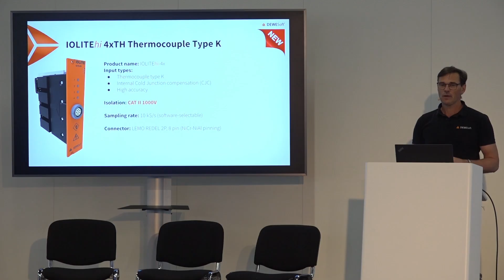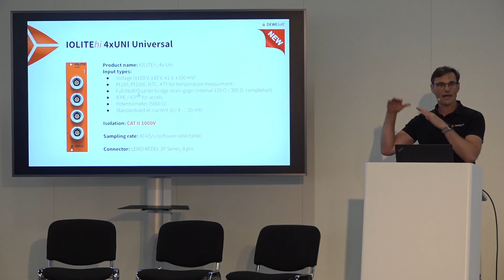The universal module I'm really proud of is truly universal, combined with high isolation Cat rating. It can measure cell voltage, module voltage, even pack voltage for some packs, all types of temperature sensors like PT100 and PT1000, full, half, and quarter bridges, IEPE acceleration transducers, potentiometers, and standardized current - all on high potential.